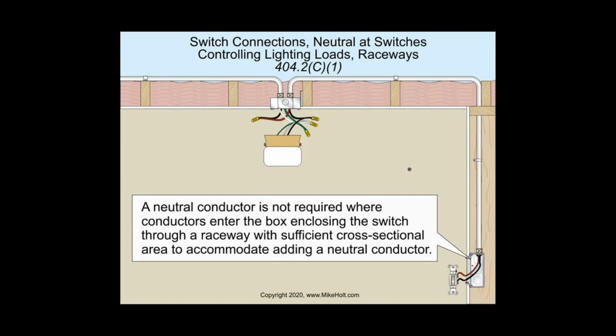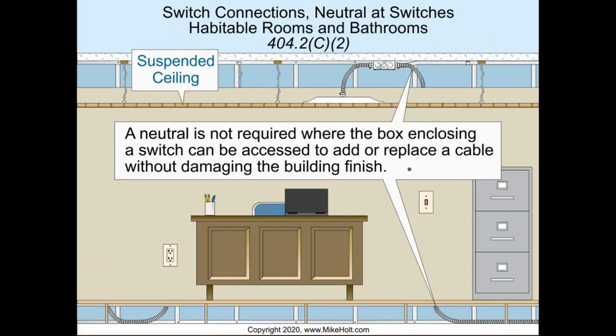All right, a neutral conductor is not required where conductors enter the box enclosing the switch through a raceway with sufficient cross-sectional area to accommodate adding a neutral conductor. So if I have EMT and I have a way to get a neutral down later if I need it, I also do not need a neutral at that location. A neutral is also not required where the box enclosing a switch can be accessed to add or replace a cable without damaging the building finish.